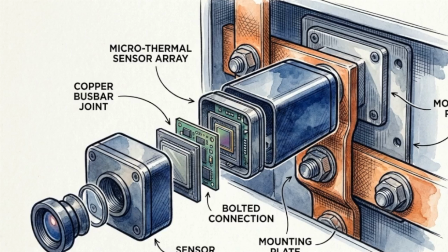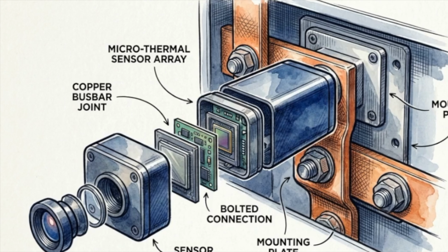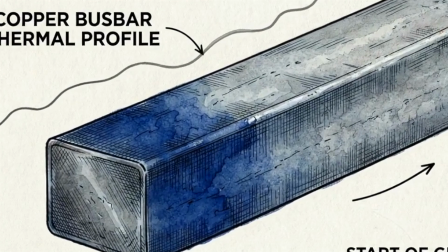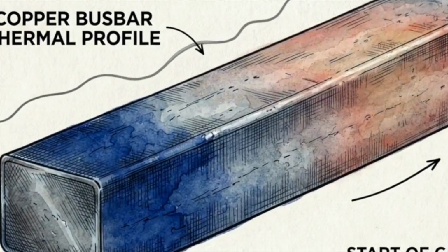To eliminate those blind spots, engineers are now embedding continuous AI microthermal sensors directly inside the high-voltage cabinets, locked onto the copper busbar joints. Because every physical object emits infrared radiation, these sensors can monitor the thermal profile of the equipment 24/7 without human intervention.